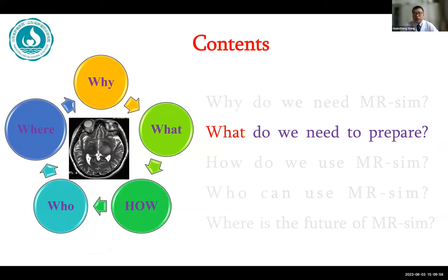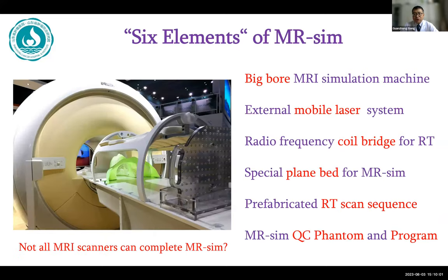The second aspect: what do we need to prepare? MRI simulation originated from diagnostic MRI, but has significant differences. In terms of software and hardware configuration, MRI simulation requires six elements: one, a large-bore MRI simulation machine; two, an external mobile laser system; three, a radiofrequency coil bridge for radiation therapy; four, a flat tabletop bed for MRI simulation; five, a prefabricated RT scan sequence; and six, MRI simulation QA phantoms.